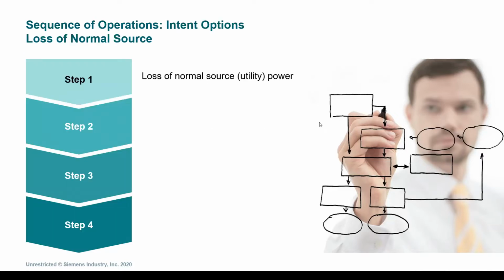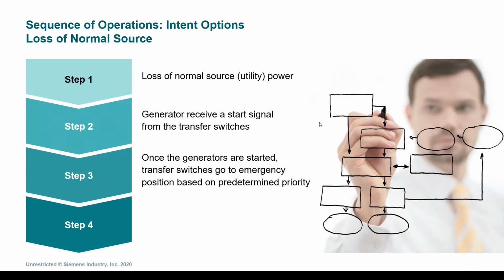So before we get into the details of the intent of the sequence of operations, let's do a high-level review of a typical process. Step 1, we lose power in the building, typically from our utility normal source. Step 2, the generator receives a start signal from the transfer switches. In step 3, once the generators are started, the transfer switches switch over to an emergency position based upon the predetermined priority. In step 4, the system maintains an alternate source status.